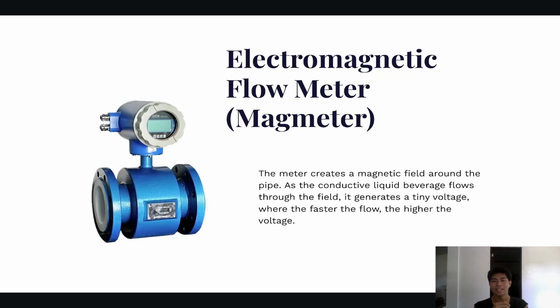Proceeding on, the electromagnetic flow meter. The meter creates a magnetic field around the pipe. As the conductive liquid beverage flows through the field, it generates a tiny voltage, where the faster the flow, the higher the voltage. The electromagnetic flow meter serves like a voltage probe which tracks or sends a signal once the conductive liquid beverage passes through the pipe where the electromagnetic flow meter is located.